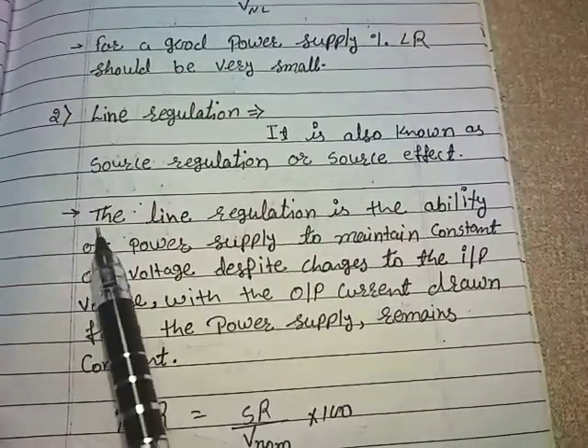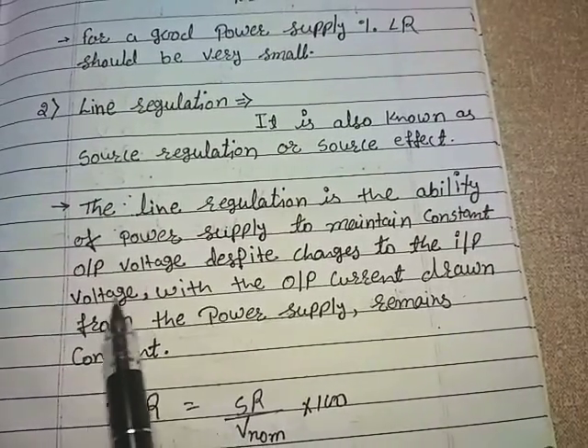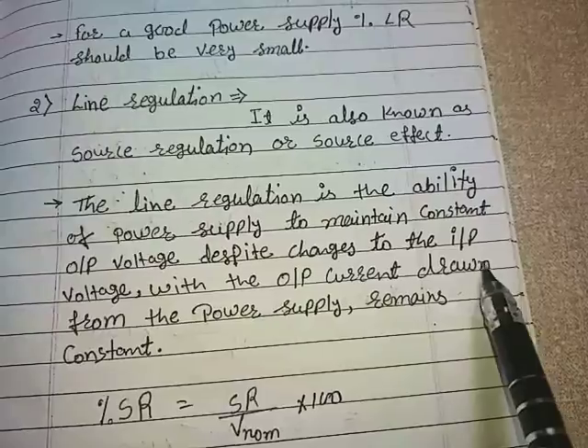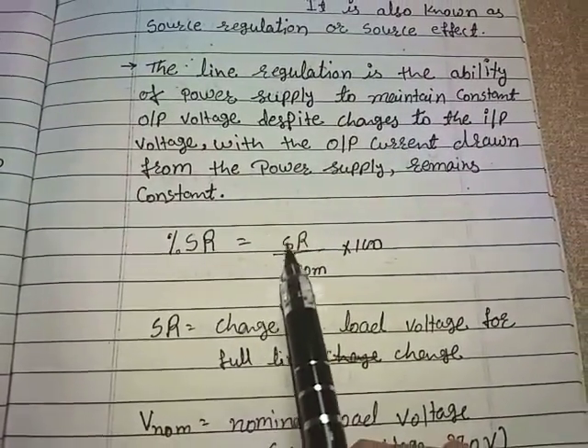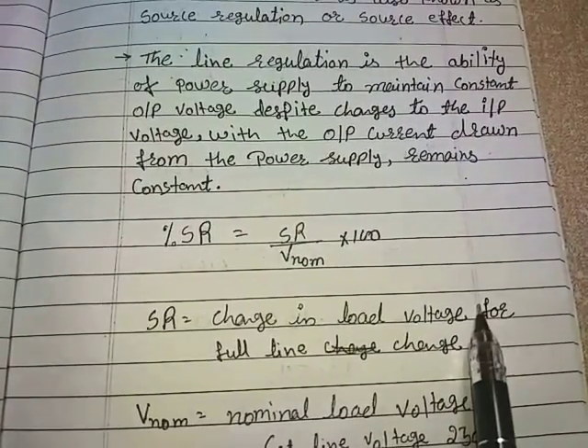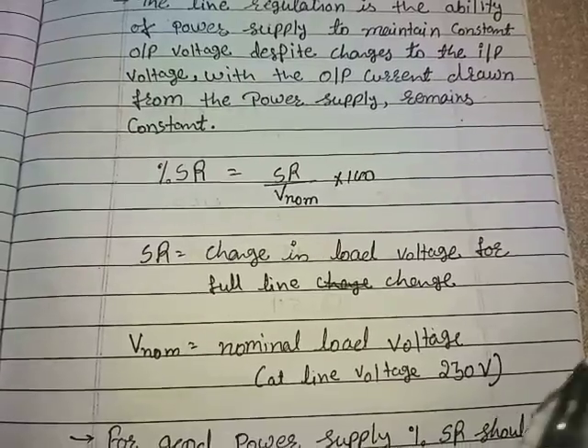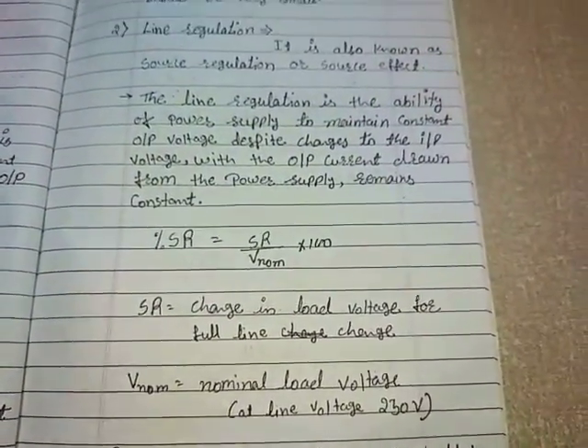Now let's move to the next characteristic: line regulation, also known as source regulation or source effect. Line regulation is the ability of a power supply to maintain a constant output voltage despite changes to the input voltage, while the output current drawn remains constant. The percentage SR is given by SR / V_nom × 100, where SR is the change in load voltage for the full line change and V_nom is the nominal load voltage, generally taken as 230 volts. For a good power supply, percentage SR should be very small.